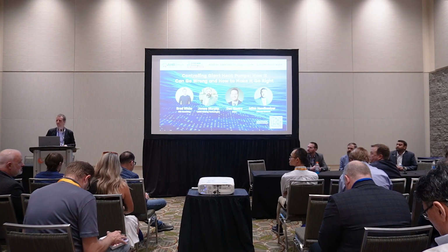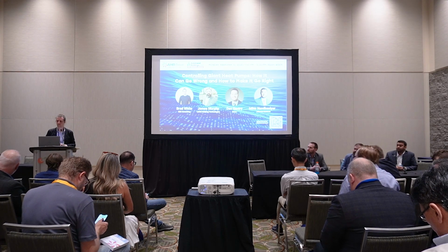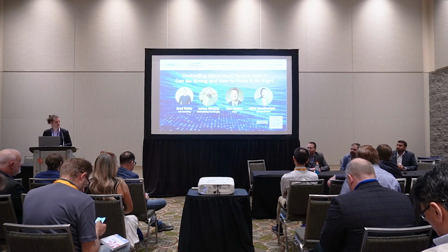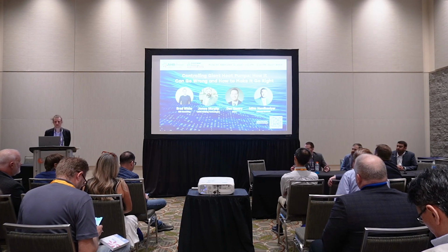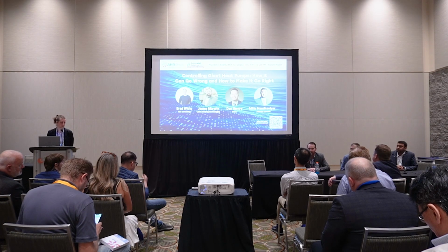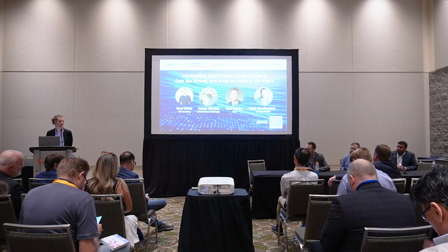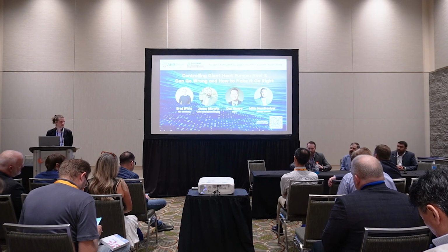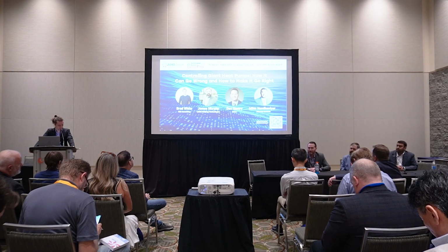Any other questions? So, controlling too much. What are some of those items that we're trying to control so we avoid that? I have opinions, but I'll hear others. One example that I've seen is the BAS shutting off a unit or shutting down the heat pump once the supply temperature has been met, instead of just letting the unit stage its compressors off or compressor down, or whatever kind of unloading it has. Or trying to force the unit into different modes too often instead of letting that play out a little longer. If you think about changing a reversing valve or changing a mode, it's going to be hard. You're starting a unit inverted and you have to work all the way back to getting your pressures right. I would say those are probably the two that I've seen.